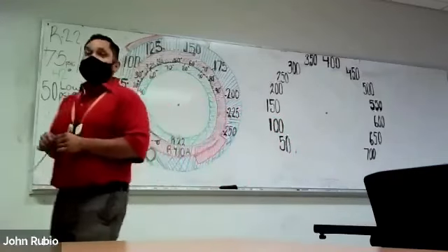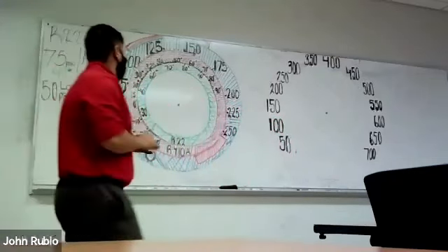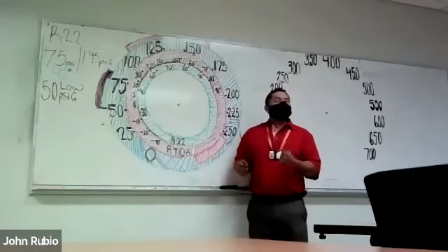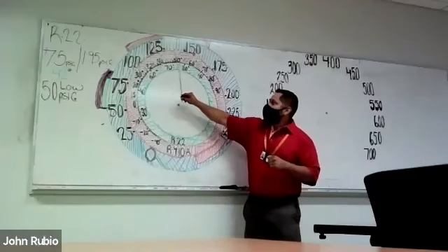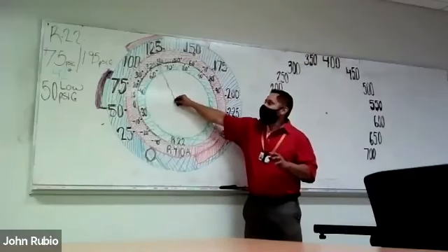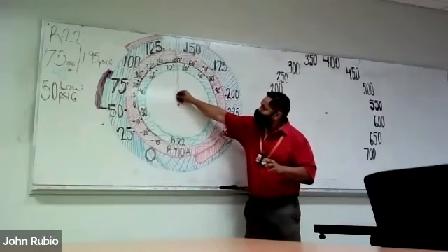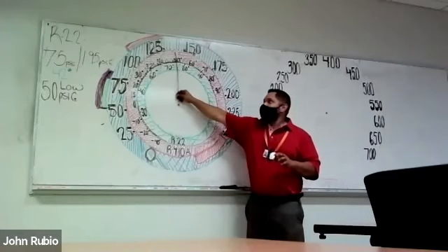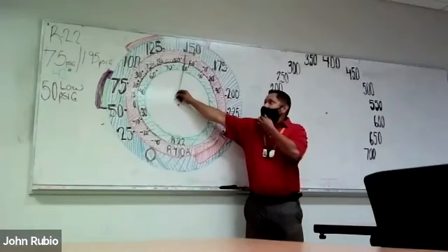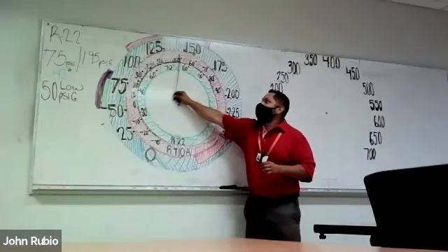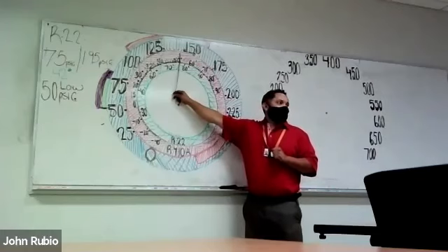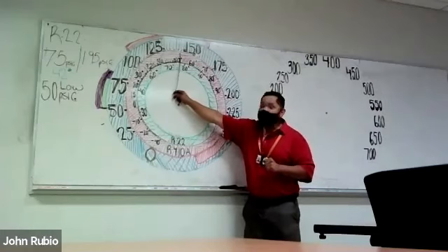When I say we have to predict whether our repairs will have an impact, if I'm here on a maintenance or no-cool, or someone says, hey, it's just not cooling that well, can you check it out? And I find my refrigerant gauge pressure is about 140, chances are I'm somewhere in my sweet spot or I'm right next to it. If I'm already here, I can't tell her, hey, I'm going to add some gas to get some performance for you, because you're pretty much there.